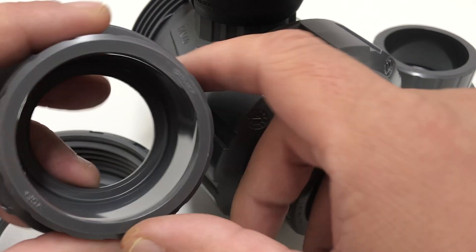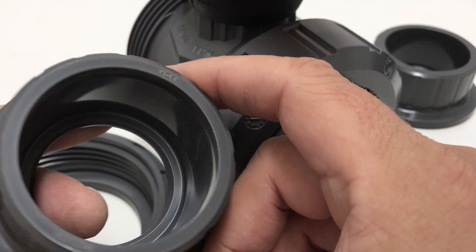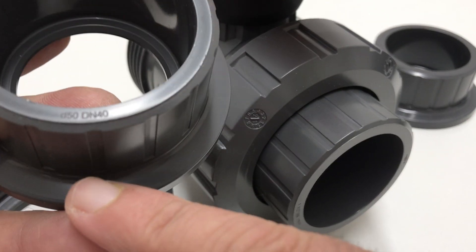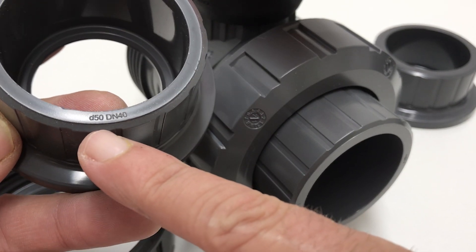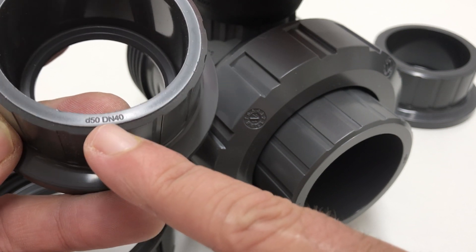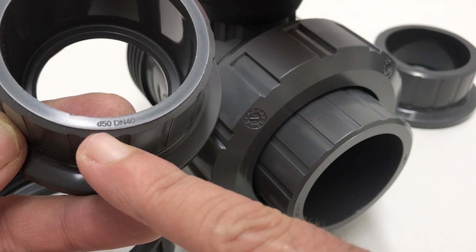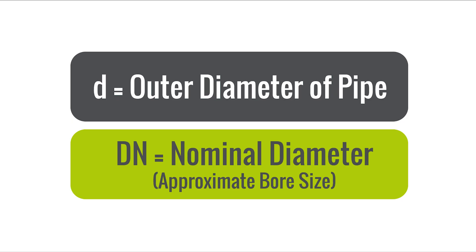Here I have a valve end taken from a metric valve. Let's have a look at these markings — the end is marked as D50, meaning it is compatible with metric pipe with an outer diameter of 50 millimeters. The DN 40 means it belongs on the DN 40 valve body. So DN references the nominal diameter of the bore, and the letter D references the outer diameter of the pipe.